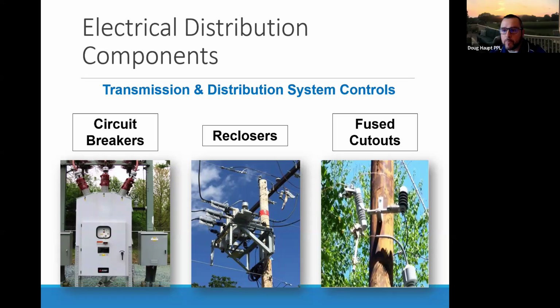And by not opening that main breaker, with that extension cord plugged into the generator and an outlet, the energy from that generator bypasses the meter and goes out to that transformer that's on the pole. And that transformer works in the opposite direction. It will step that energy up from that generator on our system to 7,200 volts. So just because that fuse opened or that Viper operated, it doesn't give you a green light to go move that wire or cut a tree. Please do not cut trees off of wires until your utility is there and told you the line is out and the line is grounded.